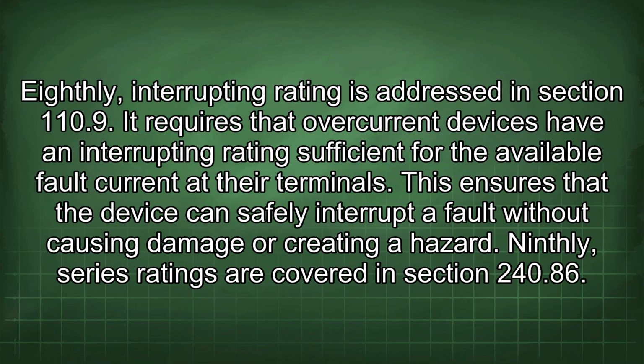Eighthly, interrupting rating is addressed in section 110.9. It requires that overcurrent devices have an interrupting rating sufficient for the available fault current at their terminals. This ensures that the device can safely interrupt a fault without causing damage or creating a hazard.